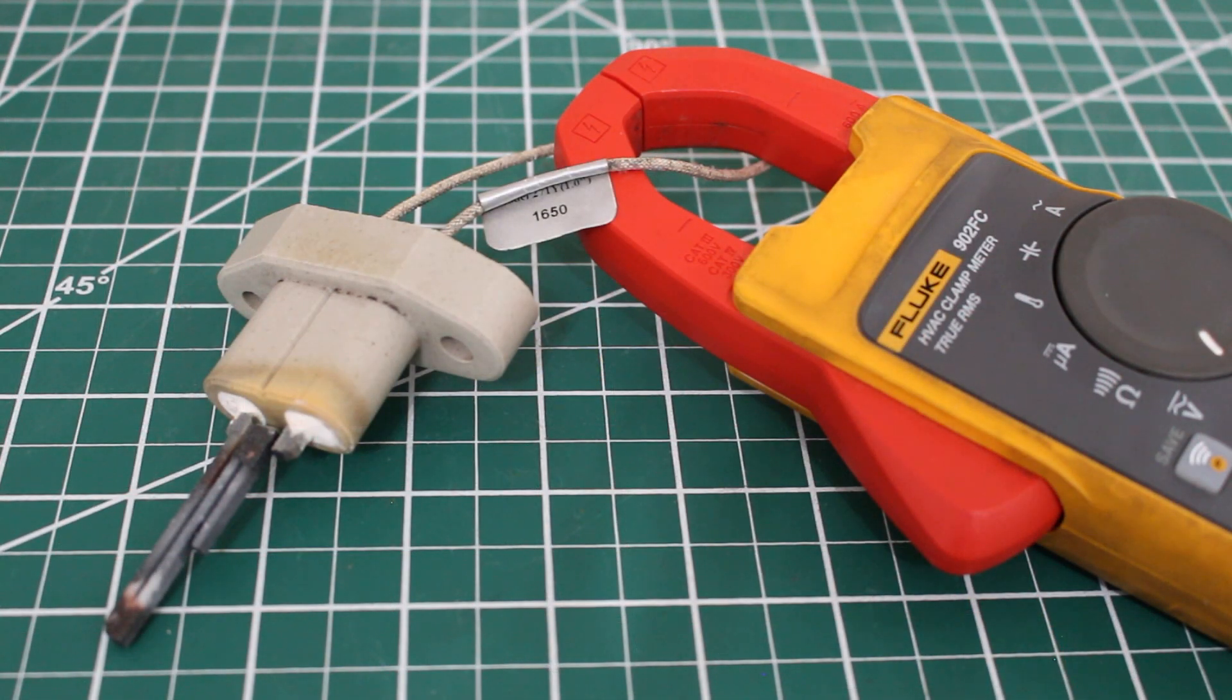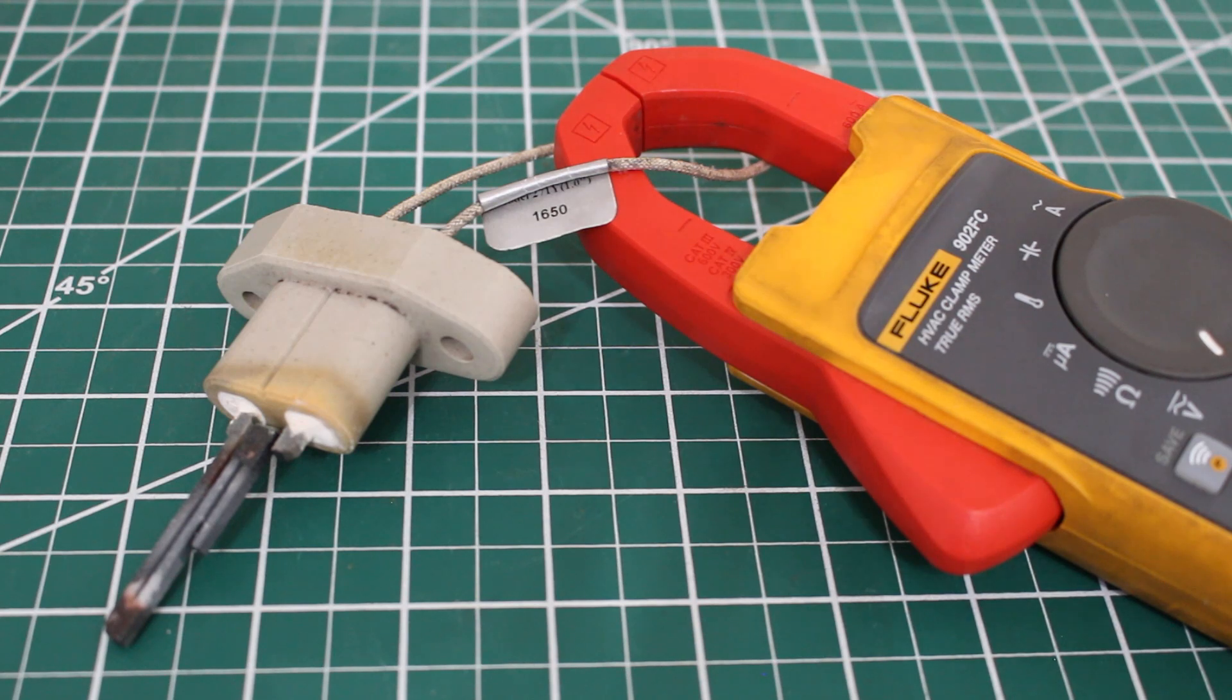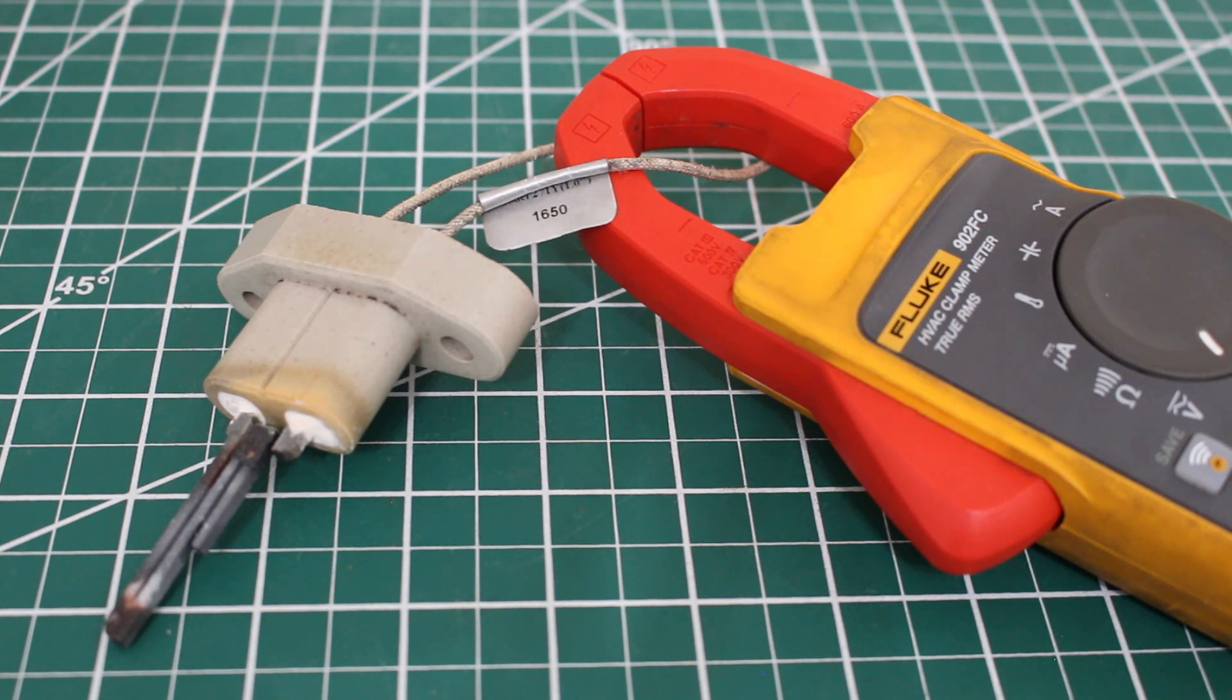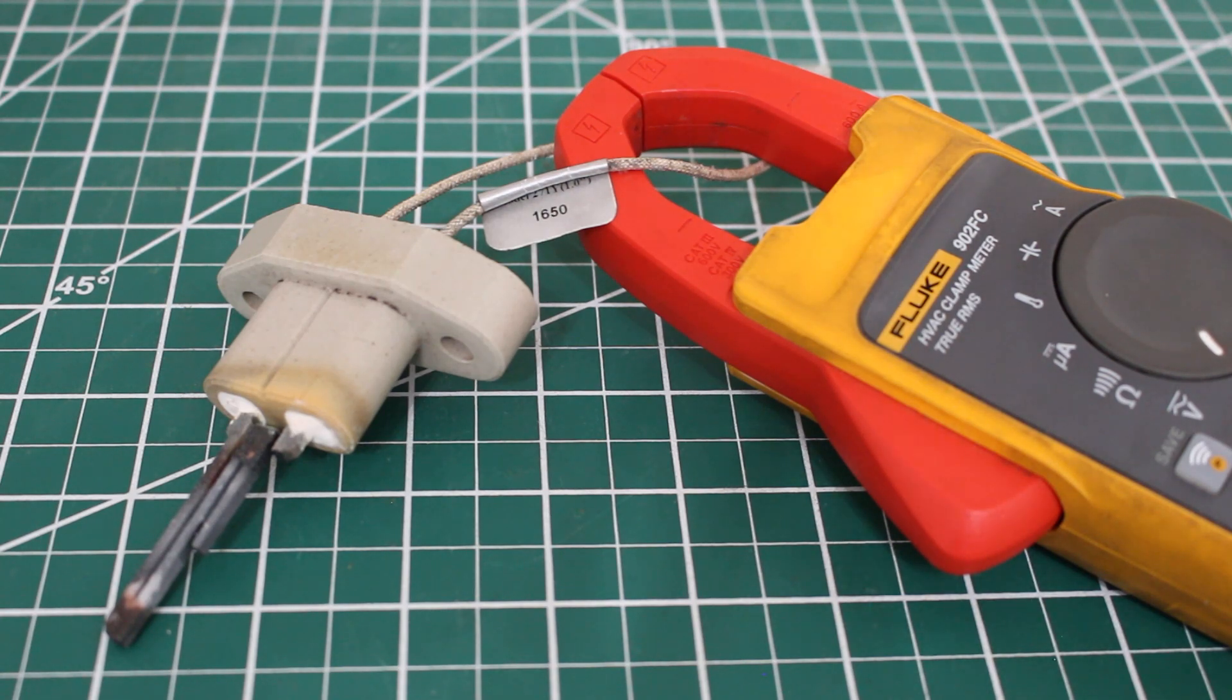Each hot surface igniter also has its own rating for amperage. These do pull amps so once voltage is applied they should be pulling amps and it's best once again to check in with the manufacturer's ratings.